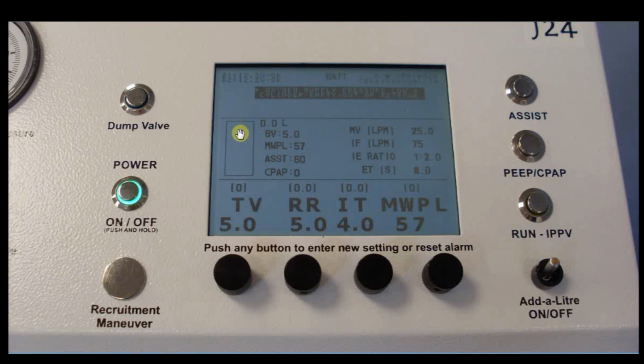Looking at the screen now, as we just said, this is the area that's represented by the piston. To the right of that we have the actual volume of gas under the piston. Then we have a value called BV, which is the buffer volume, and this takes a little bit of explaining. The buffer volume is an independent volume which, when added to the tidal volume, which is set here, forms a total which is then accepted by the machine to be the virtual bag size of the circuit.